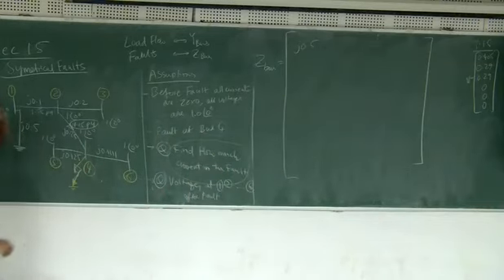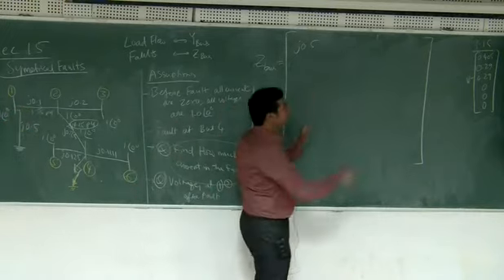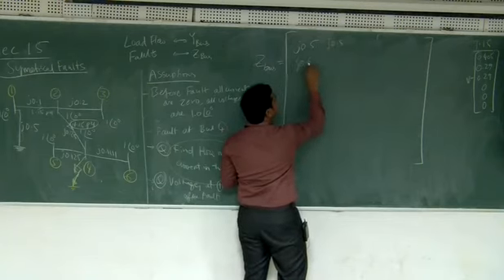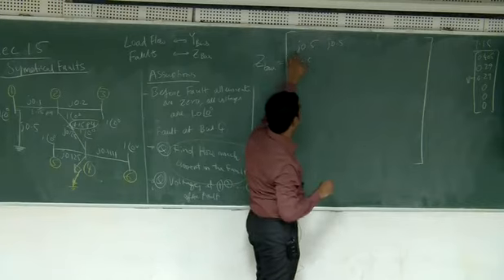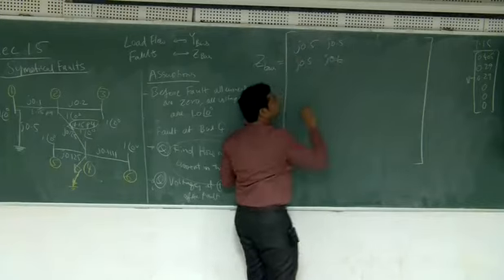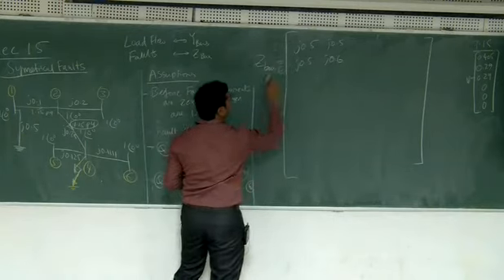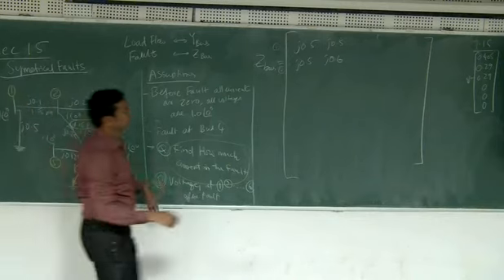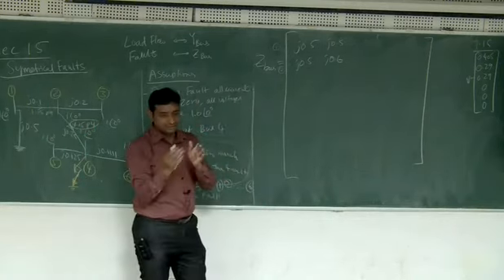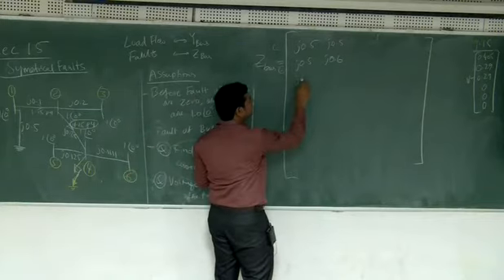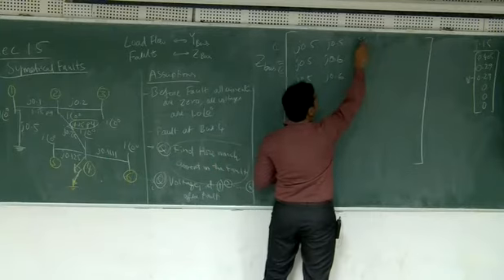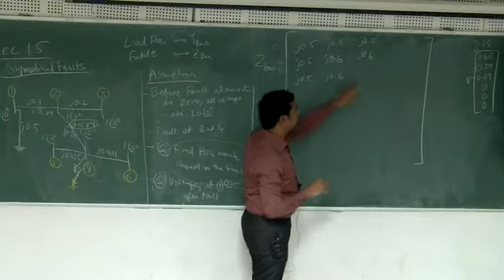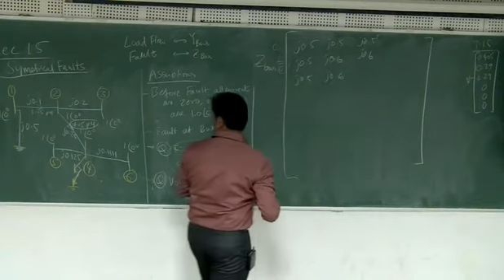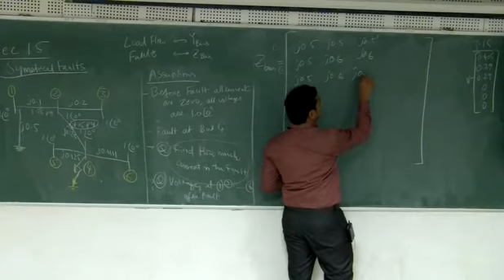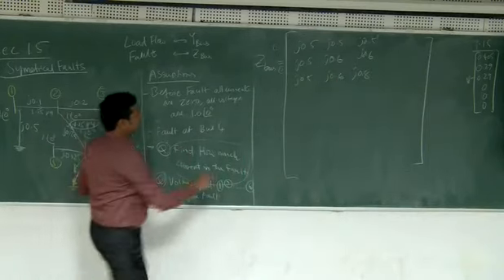Second step, adding bus 2 to bus 1. So j0.1 is added. You copy the row: j0.5, j0.5, and then you take Z11 plus Z2, so this will be 0.6. So this is buses 1 and 2. Then bus 3 is added, j0.2. It is a new bus connecting to old bus 2, so copy the second row: j0.5 copied, j0.6 copied. Now here Z22 plus the new impedance, which is also 0.2. So 0.6 plus 0.2 is 0.8. So this is the third bus added.